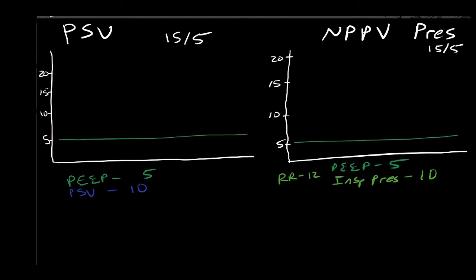Looking at these two, in PSV mode with the patient on the mask, when they take a breath in, you're going to have your minimum PEEP. They're going to go up to 15 and back down in some time increment. If they want to, they can take a little short breath, and it's going to attempt to get up to that 15. 15 is what is flowing into them. That's the pressure. Whenever they allow that pressure to enter their lungs, it's coming in at 15. It's not necessarily going to reach all the way up, but they can do it for whatever time frame they want. If they want a little teeny short breath, they can. If they want a long, drawn-out breath, they can. And so the patient is very much in control of their own breathing.